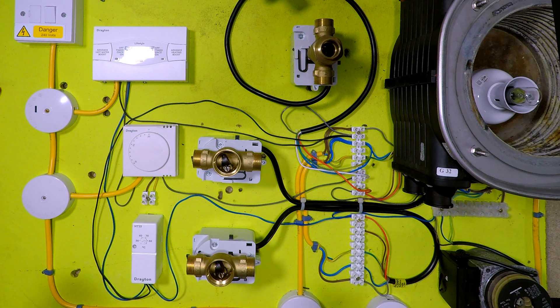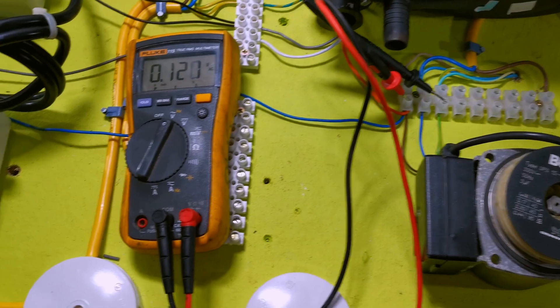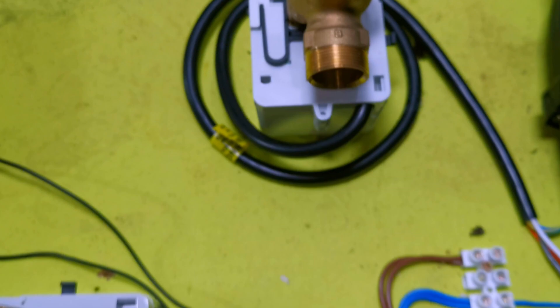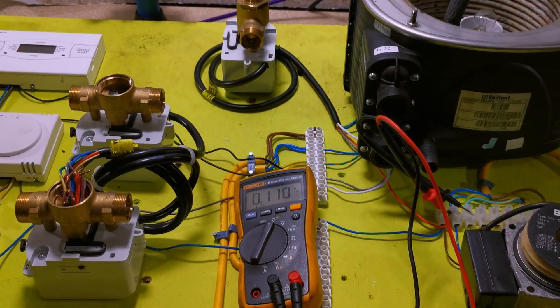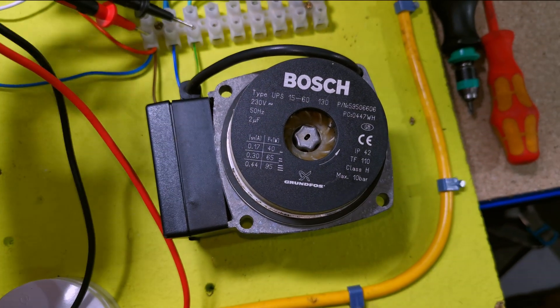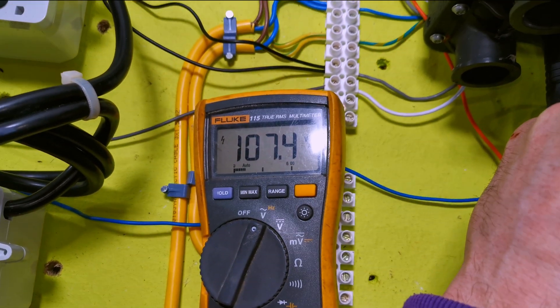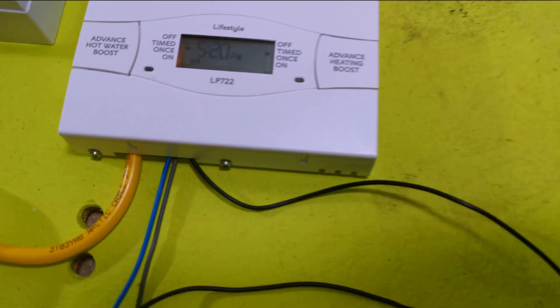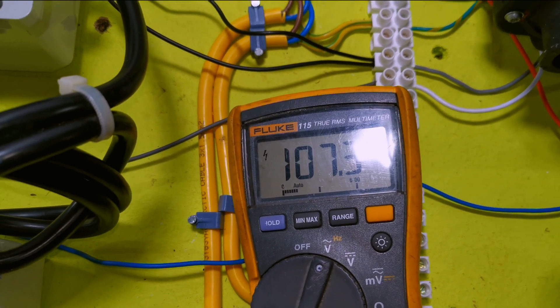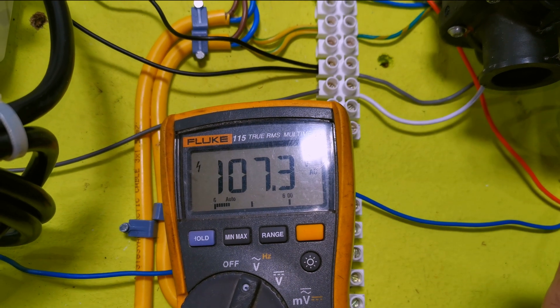Okay, so here we are, we're now going to measure the back feed voltage created by this valve being in heating only. So here we go. So as you can see with everything off, the valve is sending 107 volts down the orange.